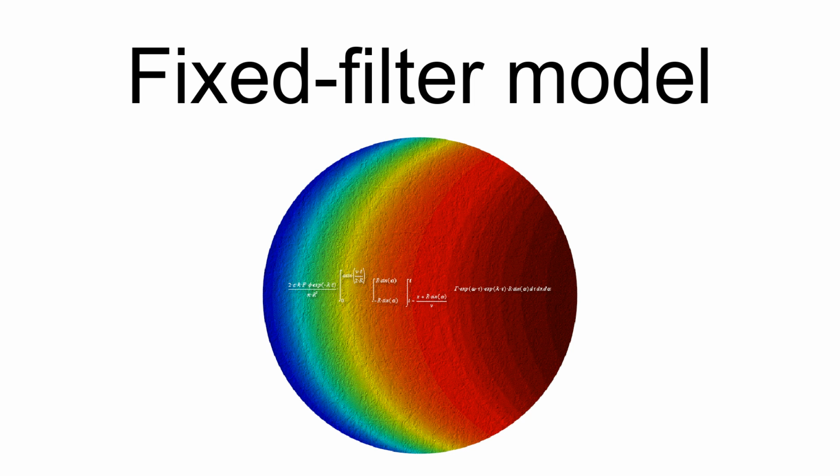The last term accounts for any initial activity on the filter medium and is usually set to 0, clean filter at time 0. The initial count rate of the monitor, before the concentration transient begins, is only that due to ambient background. If radon progeny are present, they are assumed to be at equilibrium in generating a constant count rate that adds to the ambient background's count rate. Various solutions for the time-dependent FF count rate follow directly, once a concentration time-dependence Q(T) has been specified.